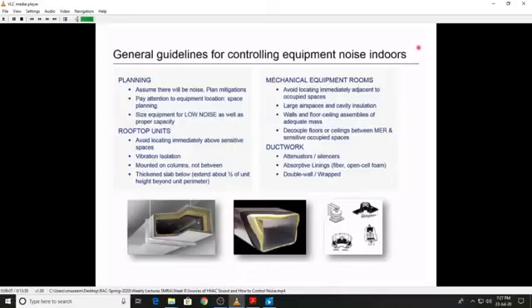For rooftop systems, you would definitely want to avoid locating immediately above some sensitive space like an office or a doctor's examination room. You need to use vibration isolation. You need to make sure that the mass, the weight and the vibration are mounted over columns of the building, not in between them. And it's often good to add a big thick mass on which the unit sits. That mass doesn't really absorb the vibration so much as it blocks its path.